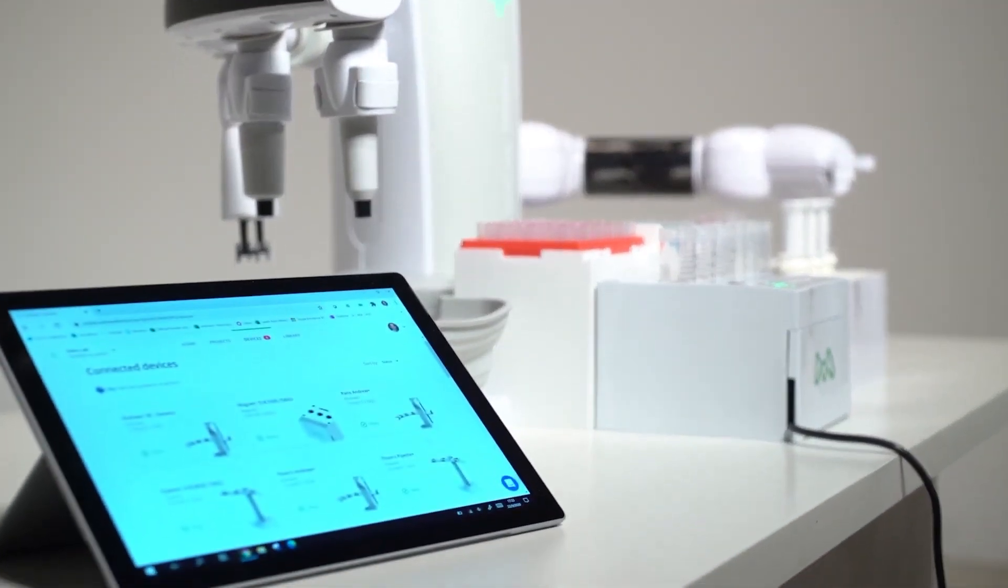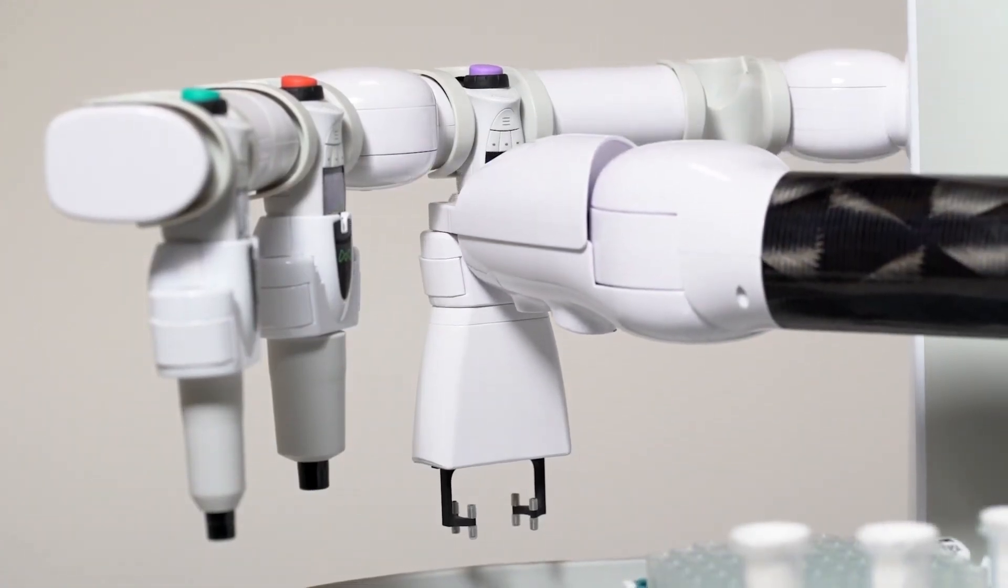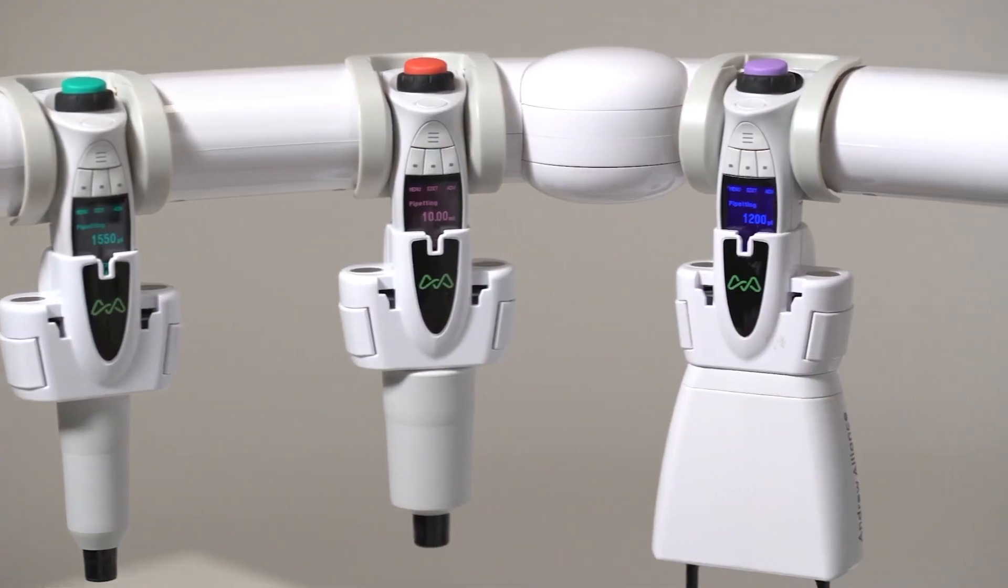I'd like to highlight some key features of the robot. You can see the robotic arm, which can select different pipettes and tools from its tool rack, enabling it to perform a wide range of liquid handling applications in an efficient and highly repeatable way. At the bottom are consumable holders called dominos, which can be freely combined according to the task at hand.